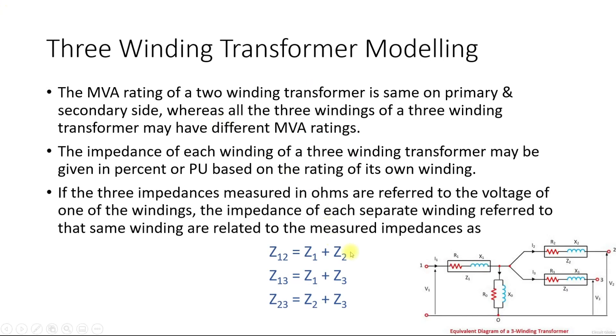A three-winding transformer, instead of two windings, has three windings. Looking at its equivalent circuit, the first winding is known as winding one or high voltage (HV), the second winding is known as winding two or low voltage (LV), and the third is known as the tertiary voltage or winding three. R0 and X0 represent losses within the transformer. Unlike a two-winding transformer where both windings share the same MVA rating, in a three-winding transformer all three windings may have different MVA ratings.